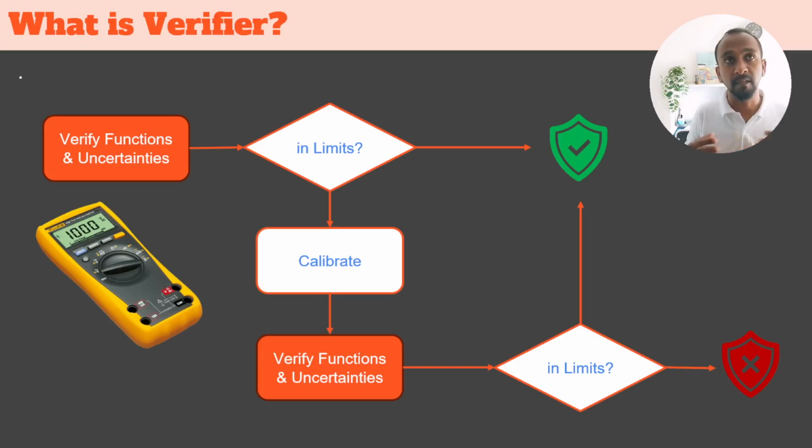In a calibration lab, you may not repeat it very often. You know by experience to what level you need to tune to bring it back. If it doesn't, you do a couple of verifications, and you decide, no, it is not good, or yes, it is good now, something like that. So what is this going to give us?